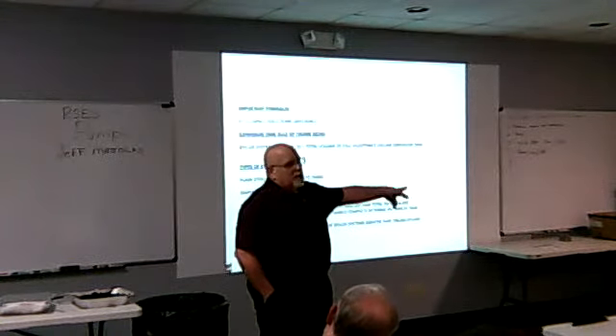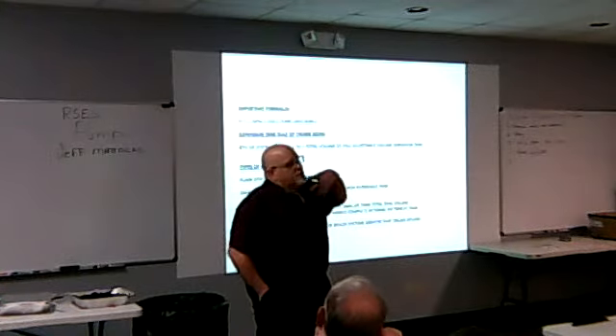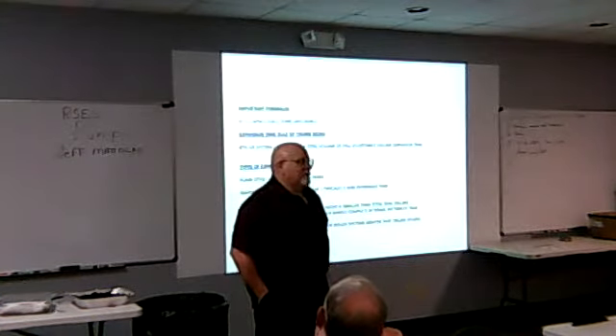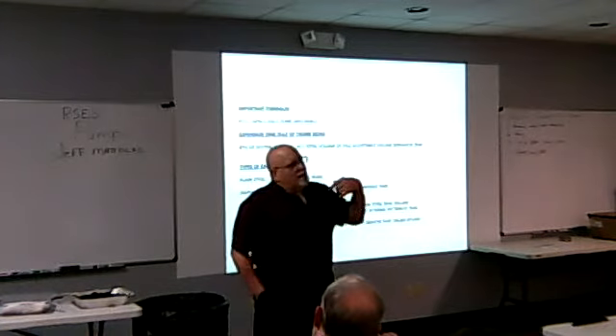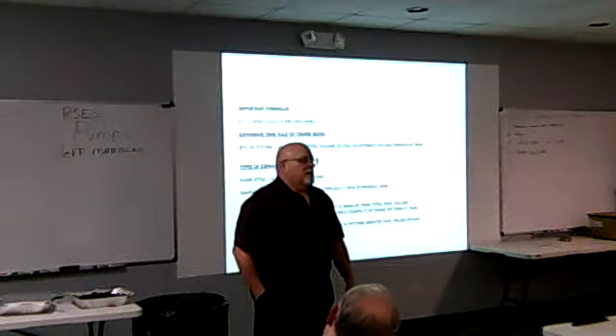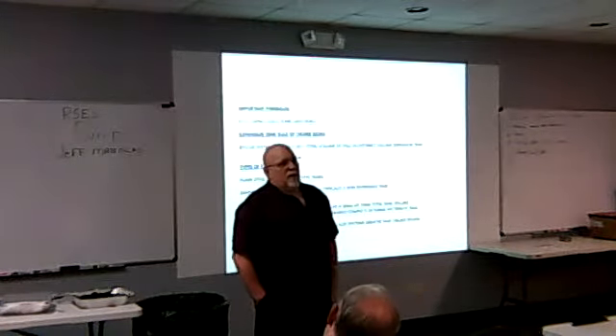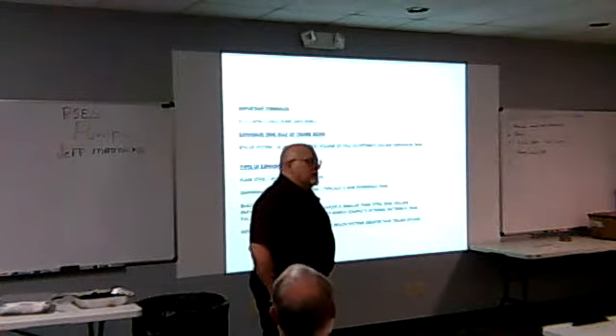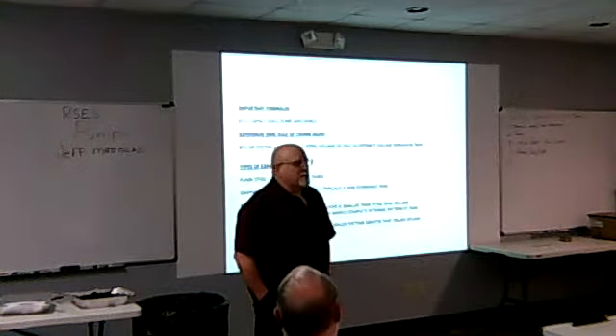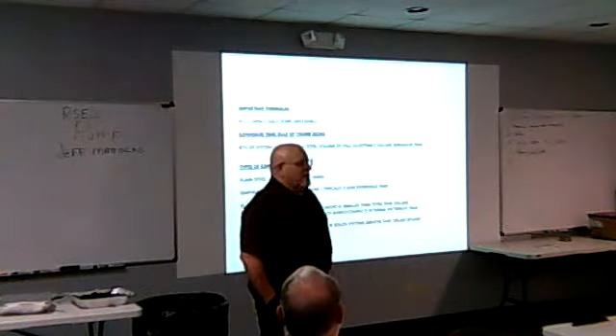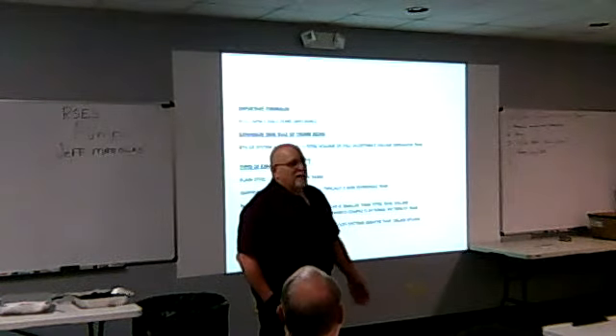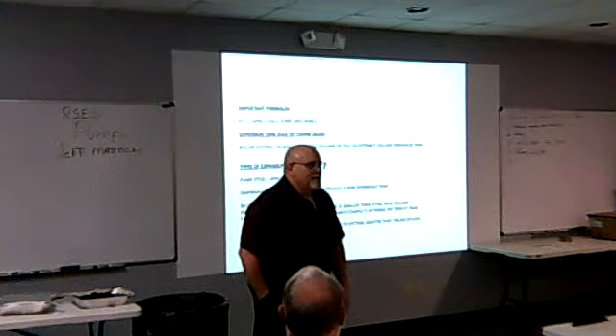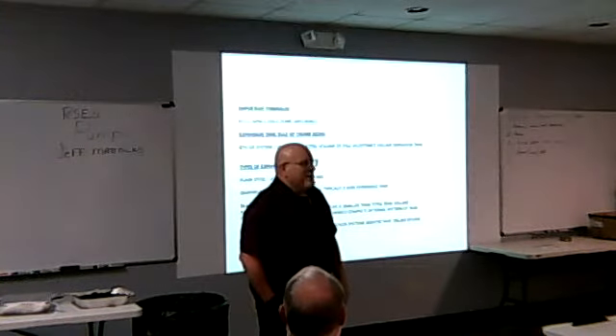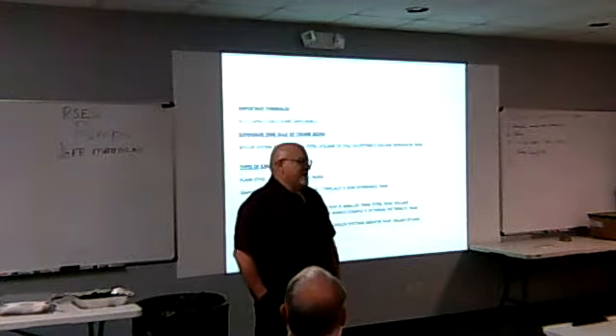They called me last week on this stuff. So many people think, well, I got a 15-pound fill, I got a 100-pound relief. Oh, your expansion tank's not working. Why? Oh, we're at 200-degree water temp. I got 100 pounds in my system now. We started at 15. I'll say, what's your relief valve setting? 125. Okay, you're good. It's a 150-pound working system.